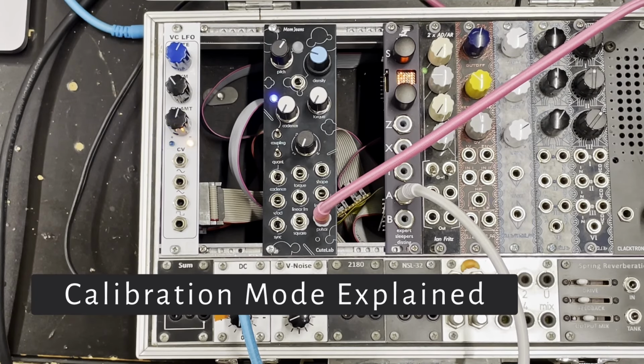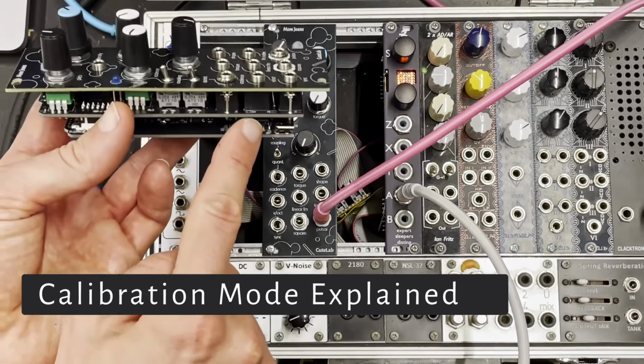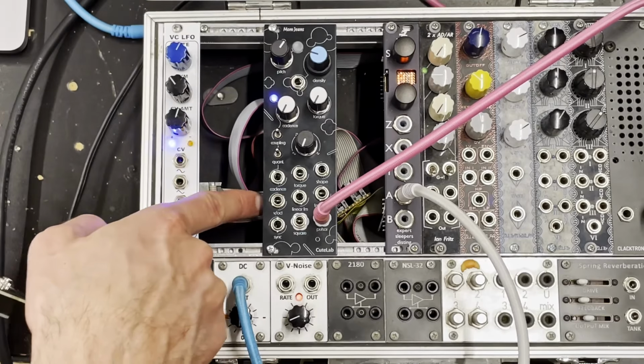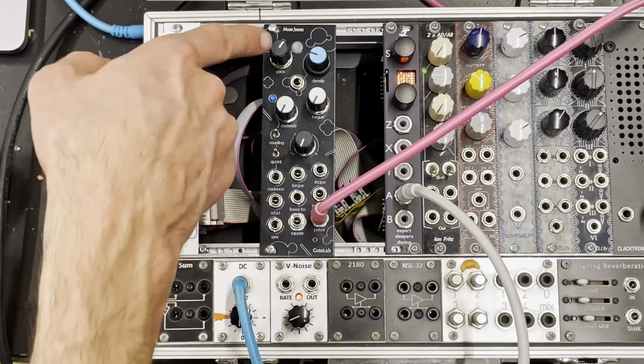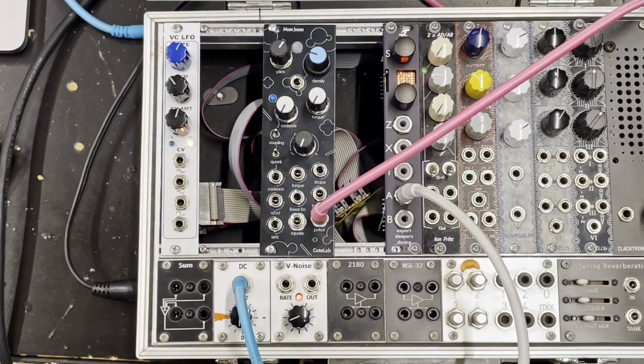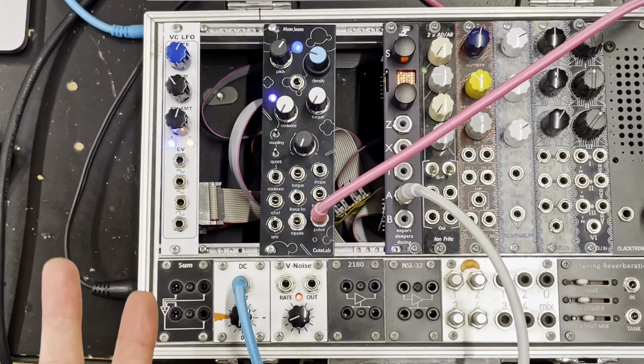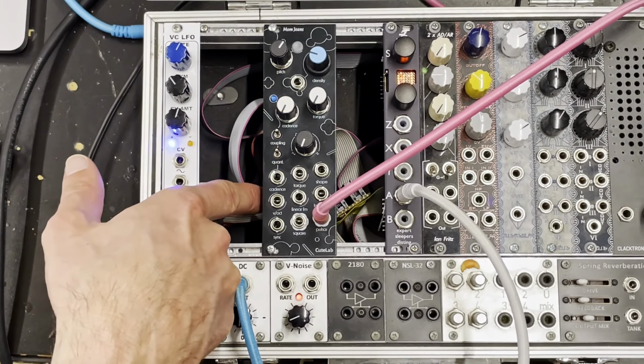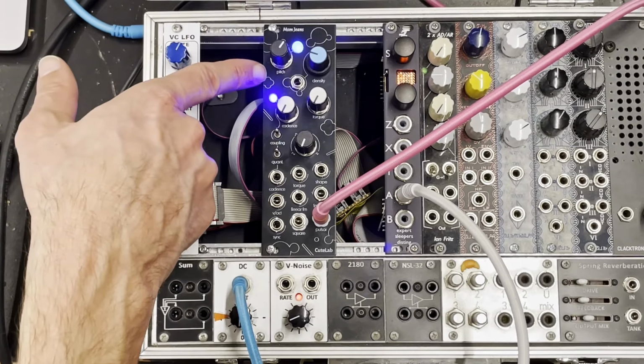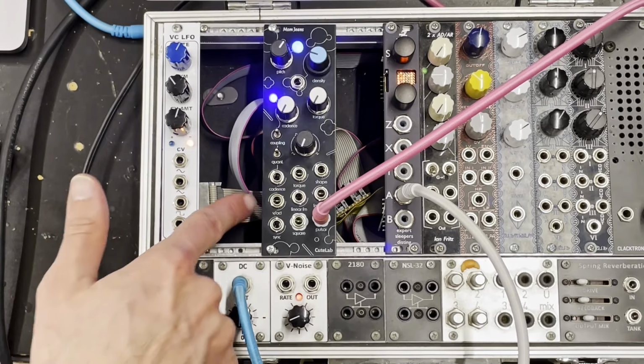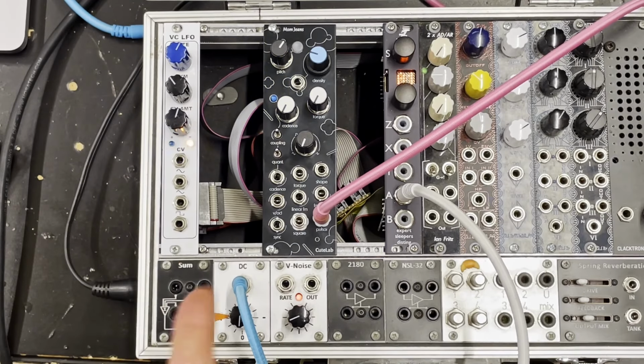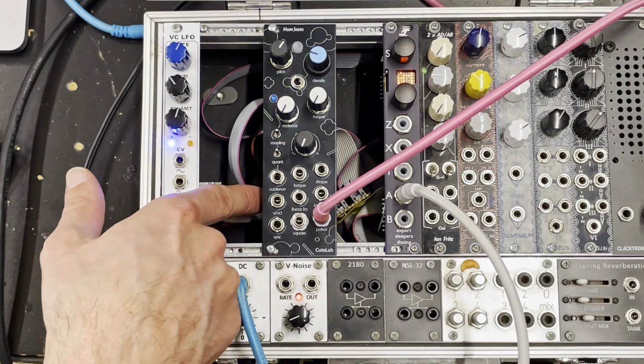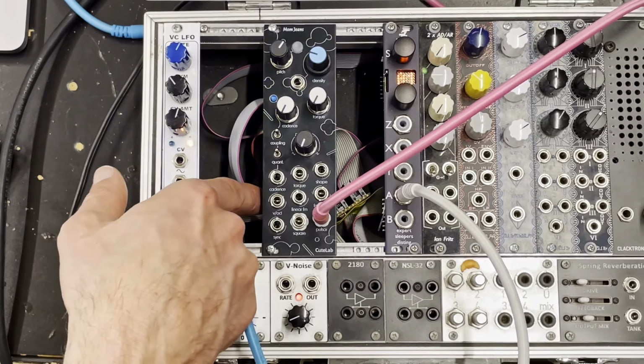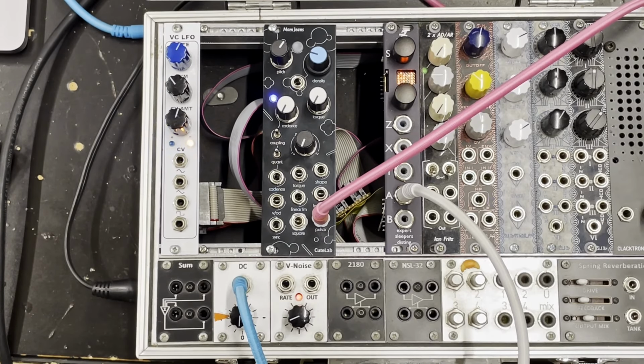To enter calibration mode, what you do is press and hold the calibration button here. When you press and hold it, you'll see these 2 LEDs start to blink like this. That means the module is in calibration mode. There are 3 calibration modes, and you can cycle between them by pressing the calibrate button. Now I'm in calibration mode 2. You can see that because the LEDs are blinking twice and then turning off. And in calibration mode 3, they'll blink 3 times and then turn off. Once you go from calibration mode 3, you push the button 1 more time, and this takes you back into normal module operation. When you do that, the module saves whatever values it received during calibration. So that's also how you write calibration.